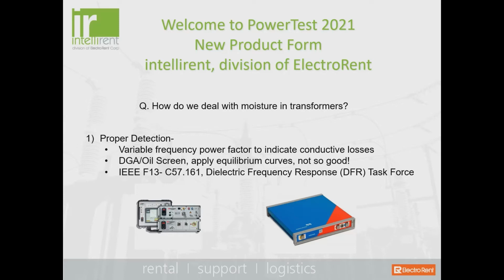We can apply a variable frequency power factor to indicate conductive losses, which could be moisture, and that could be your first indication. Secondly, and most popular, is a DGA or oil screen, where we apply equilibrium curves to find the right mixture of moisture between the insulation and the oil. This really isn't all that reliable, but can give you a good indication. Third, and something that we propose in terms of a rental solution, is a dielectric frequency response analysis approved and recommended by IEEE C57.161. So let's say that you do find excessive moisture in your insulation.